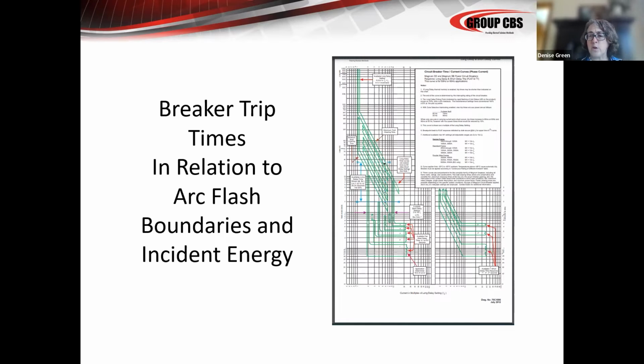So this is a standard breaker trip curve. If you've never seen one, it shows all the long time bands and instantaneous bands on this particular curve for a standard solid state trip unit. This is from a coordination study that shows multiple devices all layered on the same drawing so that coordination can be properly made between feeder breakers, main breakers, fuses, primary breakers, and all the components that feed that circuit.